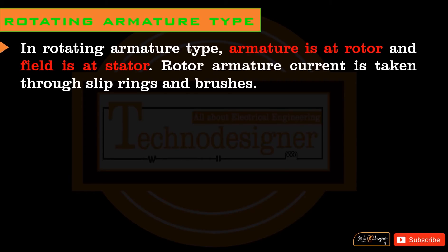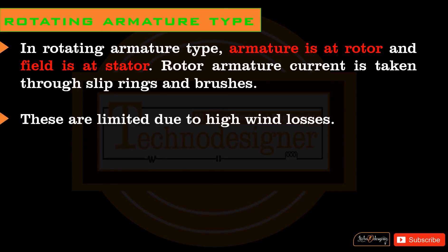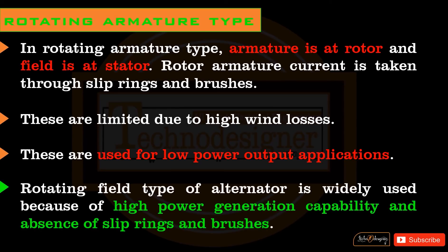Rotating armature type: In rotating armature type, the armature is at the rotor and the field is at the stator. Rotor armature current is taken through slip rings and brushes. These are limited due to high wind losses and are used for low power output applications. Rotating field type alternators are widely used because of high power generation capability and absence of slip rings and brushes.